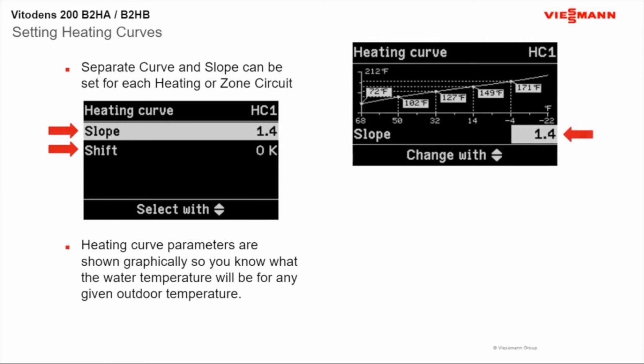So the neat thing with our heating curves, while you're adjusting them, you can see your actual temperatures change. So the slope is going to do mostly here, how fast you're going to go to your hotter temperatures at the top. So as you can see, as you're looking at this here at -4 degrees, we go up to about 171 degrees. But once it hits -4 degrees outside, we'll be heating that house with 171. So that's where you're going to make sure that on the coldest day of the year, that's the way I always set up my heating curves, set it to that highest temperature. So as soon as you say in this area, coldest day might be -4 maybe. Or even here at 14, if you want that 180 here, then you're going to play around with your slope.